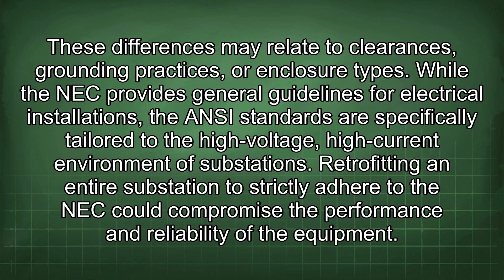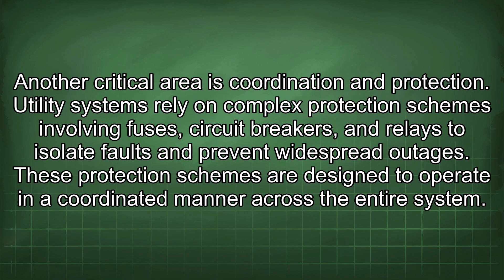Utility systems rely on complex protection schemes involving fuses, circuit breakers, and relays to isolate faults and prevent widespread outages. These protection schemes are designed to operate in a coordinated manner across the entire system. Changing the characteristics of one component to comply with a specific NEC requirement could disrupt the coordination of the entire system, potentially leading to more extensive outages or equipment damage.